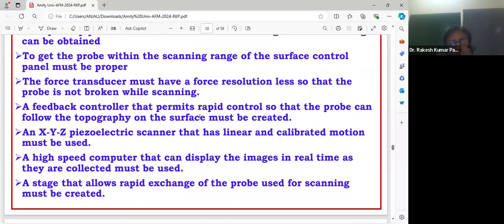A feedback controller that permits rapid control, so that the probe can follow the topography of the surface, must be created. There should be proper feedback mechanism, proper feedback control. Otherwise, it will be very difficult to get the signal from the AFM. Here we use an XYZ piezoelectric scanner that has linear and calibrated motion. So whatever piezoelectric scanner we are using must be calibrated properly. We need to use high speed computers that can display the images in real time, because here we are observing real time images. Your system should be faster.